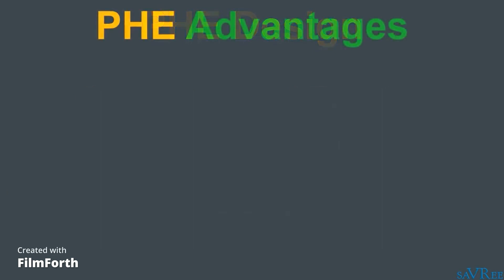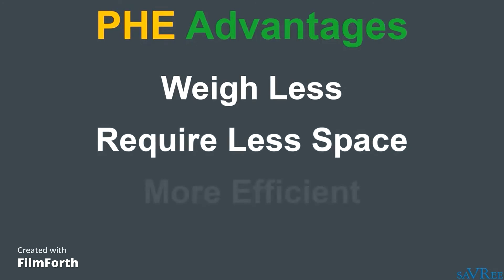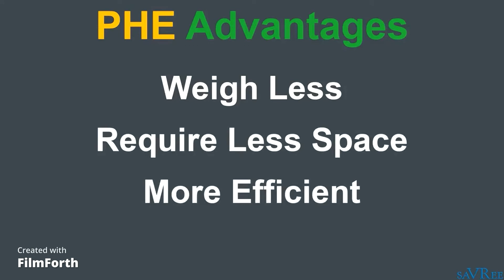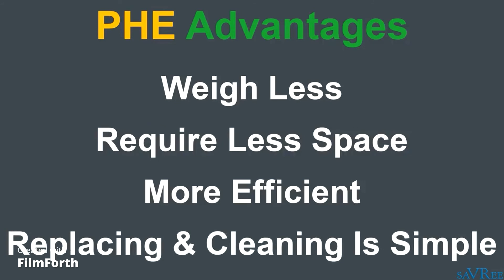There are numerous advantages associated with plate heat exchangers. Plate heat exchangers weigh less, require less space, and are more efficient compared to other heat exchanger designs of the same size. Replacing and cleaning of the plates is a simple task because the plate stack can be opened easily. And unlike shell and tube heat exchangers, plate heat exchangers do not require additional space for dismantling.